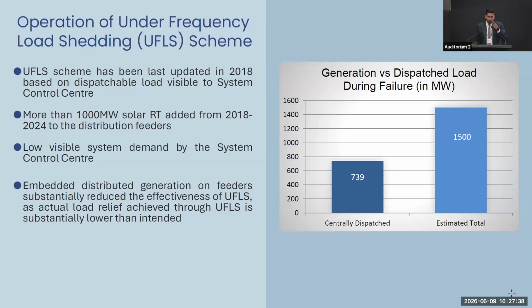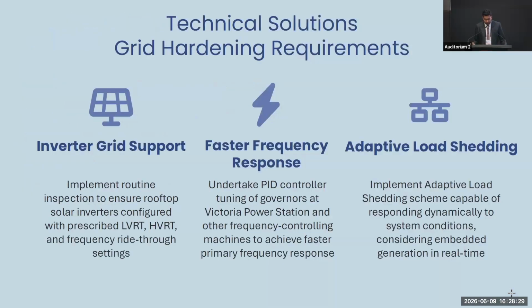As I have mentioned earlier, all 5 stages of the under-frequency load shedding scheme were activated in response to the system frequency drop. But the frequency continued to decline despite all these schemes being activated. These schemes are supposed to activate and cut the loads when the frequency is dropping. During our investigation, it was revealed that the under-frequency load shedding scheme was last updated in 2018, and that was based on the dispatchable load visible to the system control center. That is the central control center of our country. And we got to know that the desired output has not been given by that.